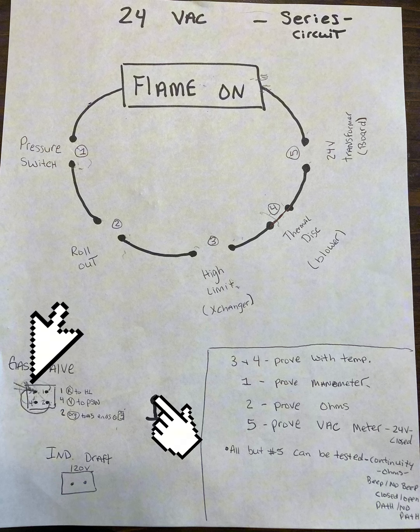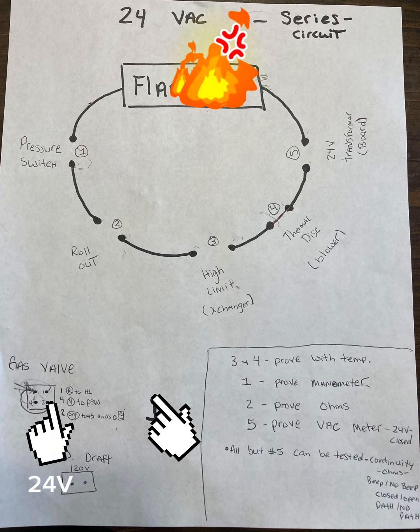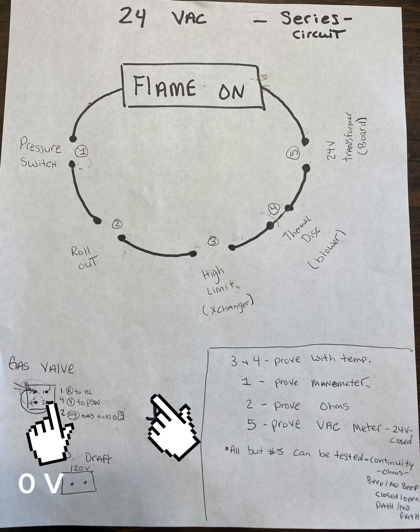So, we can tell real fast if it is your gas valve if all of a sudden you're losing flame after running for 2.5 minutes, but all of the safeties are staying closed. You can go to this smart valve here and you can put a prong, using the hopscotch method, go to a ground and go right into pin number 2, and you can see it coming from the board, right, directly. And when you lost your flame, did you also lose 24 volts there?